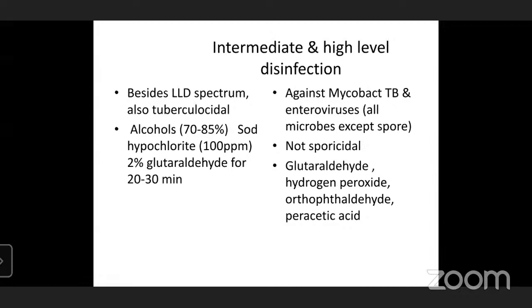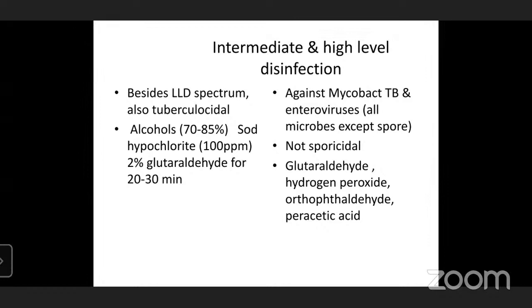Now, how do intermediate and high level disinfection differ? For example, if you are using glutaraldehyde for disinfection of a particular Ambu bag or a particular equipment, it depends on the contact time. If your Ambu bag is placed in the drum with 2% glutaraldehyde for say 30 to 60 minutes, it becomes intermediate level disinfection. If the immersion time extends beyond 1 hour, say 2 to 6 hours, that is called high level disinfection.